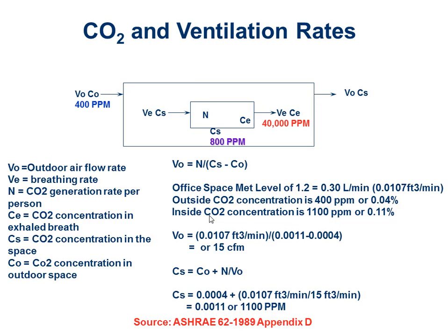All right, so this is the magic. These are the formulas in the ASHRAE standards that basically allow us to use CO2 sensors to ventilate spaces. Not only does the ASHRAE standard allow us to do it, the ASHRAE standard and its ventilation rates are based on this fact. This is how the numbers in the table were derived.